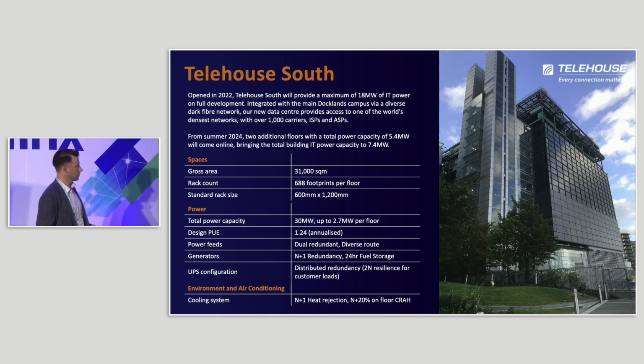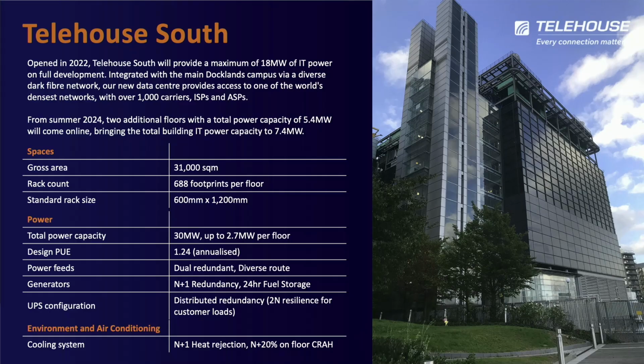A few metrics on the building itself: the gross area is 31,000 square meters. We have 688 footprints per floor - that's in flux at the moment, it's kind of going up a bit through design, which I'll touch on when we get to the photos at the end. Standard rack sizes are your usual 47U, so 600 by 1.2, 30 megawatts with 2.7 megawatts of IT power per floor. We have a design annualized PUE of 1.24.